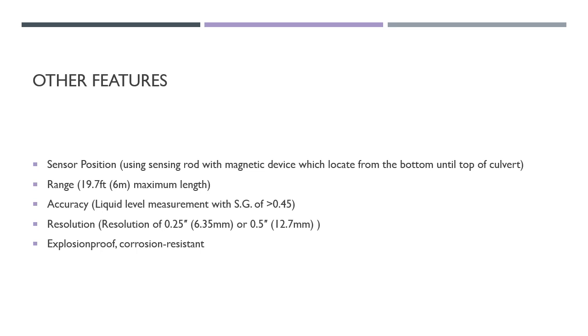We also discuss other features of the magnetic flow level transmitter. The sensor positioning uses a sensing rod magnetic device located from the bottom to the top of the culvert. The range is 19.7 feet, which is 6 meters, at maximum length. Regarding accuracy, the liquid level measurement requires an SG of more than 0.45. The resolution is 0.25 inches (6.35 mm) or 0.5 inches (12.7 mm). It is also explosion-proof and corrosion-resistant.